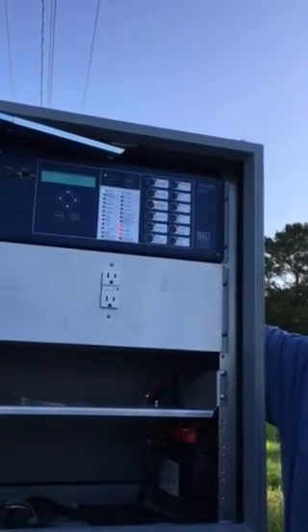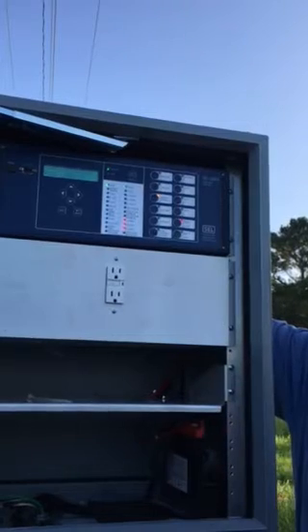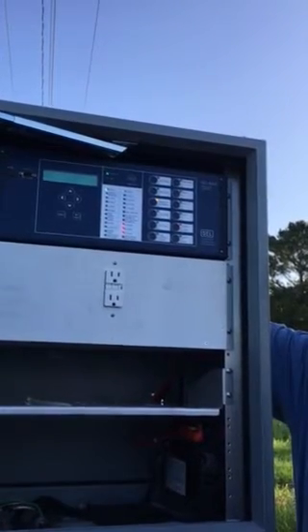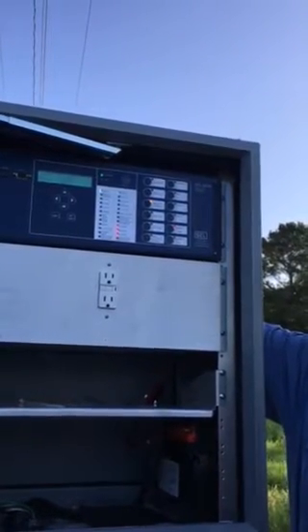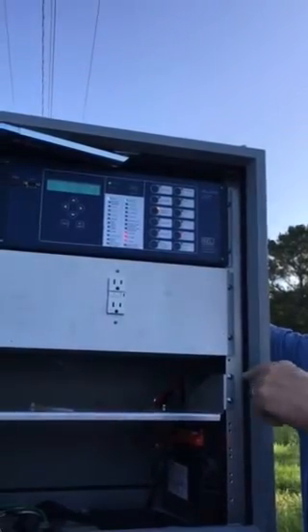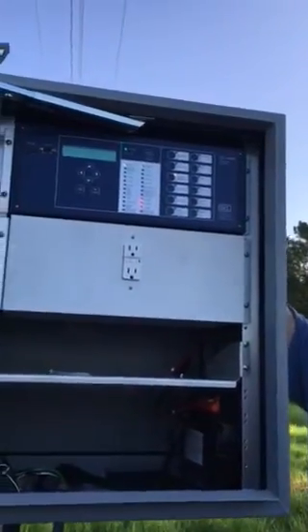If it operates a station breaker, it's going to open this. Yeah. And it's going to tell it to close back? Definitely. It's on SCADA, so dispatch can close it back, but it's got to be closed back manually. It's not set up like a recloser where it's going to see a fault, open, then close back, try it. Once it sees that fault, it's open.